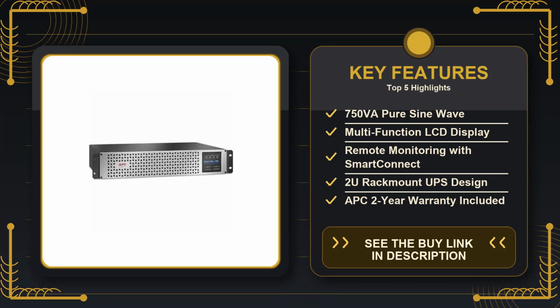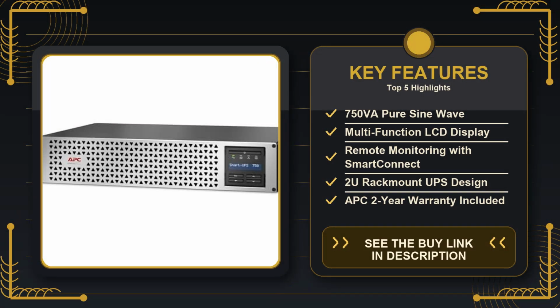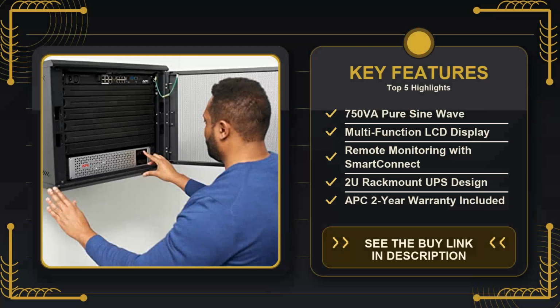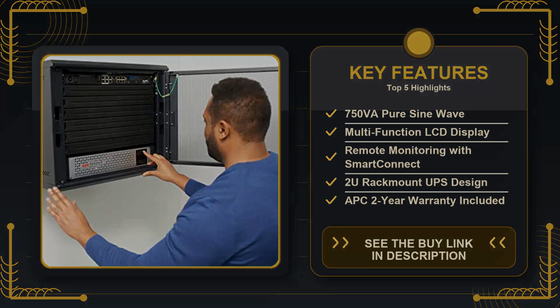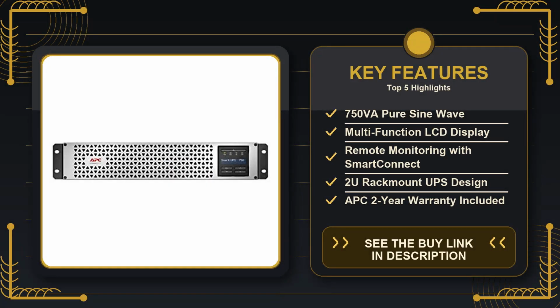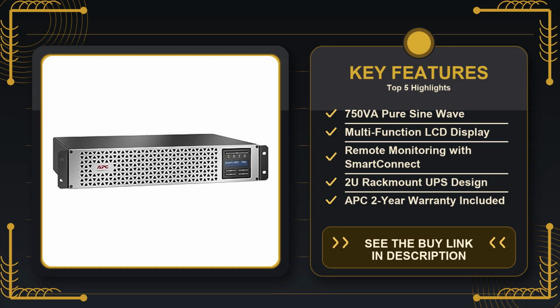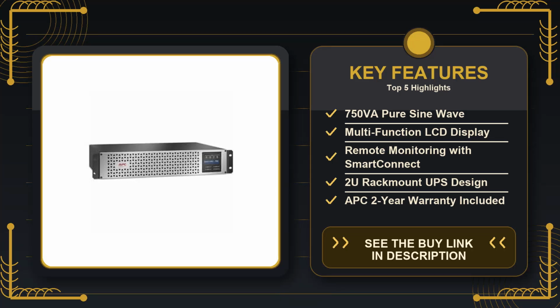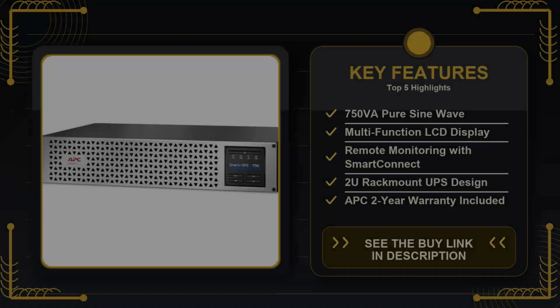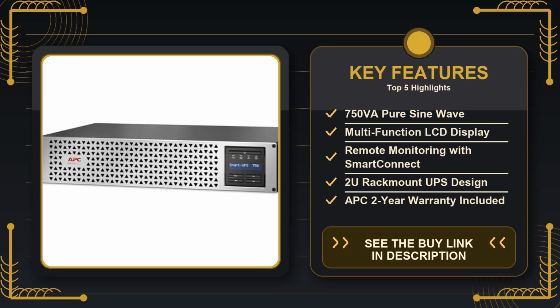In practice, this means you can log into a web portal or use the APC mobile app to see battery status, load percentages, and even receive alerts if the UPS switches to battery mode. I tried it on a laptop while the mains outage hit. The app pinged me within a few seconds, showing the load at around 45% and the remaining battery time. That instant visibility can be a lifesaver if you're not sitting right next to the unit. Think of a remote office or a server room where you're monitoring several devices. The remote monitoring is secure and doesn't require any additional hardware beyond an Ethernet cable, which is better than some older UPS models that need proprietary dongles.